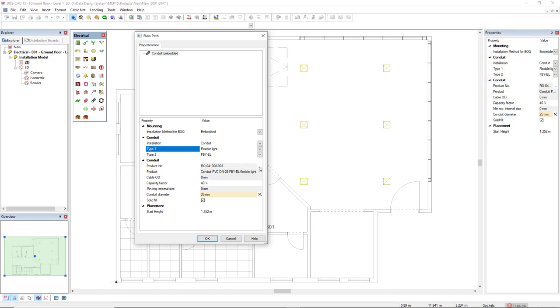By clicking on the three dots button, we open the product database of conduits. I have selected a conduit of 25 millimeters, and below we see the start mounting height at 1.252, which is the top surface of the board in which I will start the conduit.